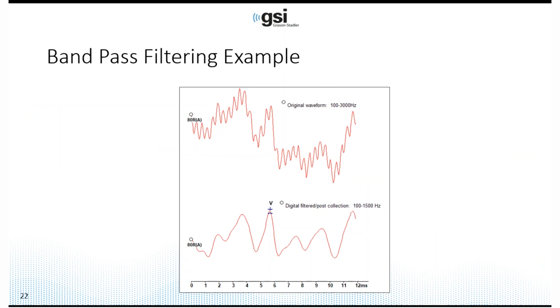The top waveform, I collected data using filter settings of 100 to 3000 hertz, and I have some high frequency noise superimposed on my ABR. So to apply a digital filter after I was done collecting, I went and launched the filter window, selected bandpass, and entered 1500 hertz as my low pass filter. And this is what the result looks like. So you can see that I clearly have some electrical artifact in my waveform between 1500 and 3000 hertz, so in that frequency range.